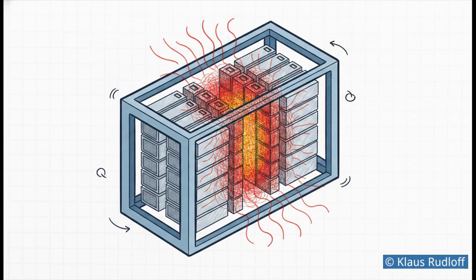Now you might be wondering, where are these vulnerable areas exactly? It's specifically the central and rear rack positions that routinely fall victim to these hidden micro-hotspots. Just visualize the physical layout for a moment. The cool air comes in, but by the time it navigates this dense maze of modules to reach the deep center or far rear of the enclosure, it's either lost its velocity entirely or already absorbed way too much heat. These core positions essentially become trapped heat zones.